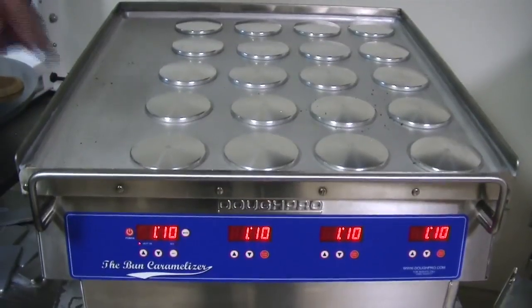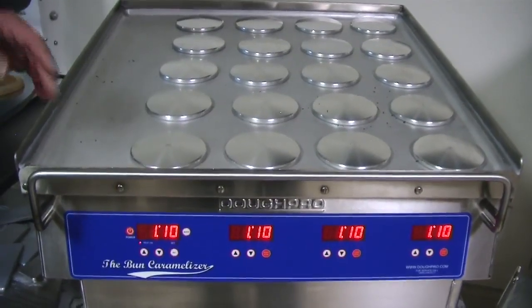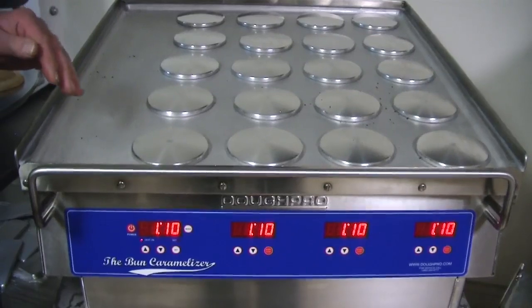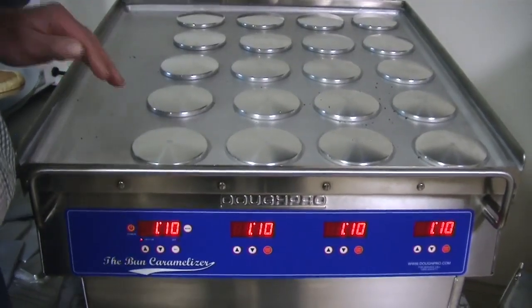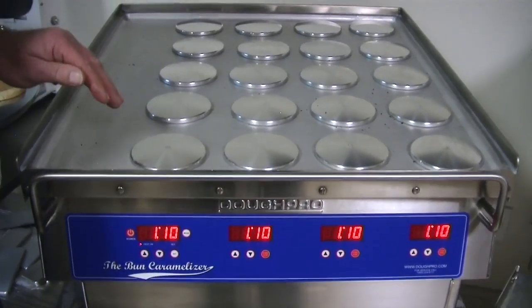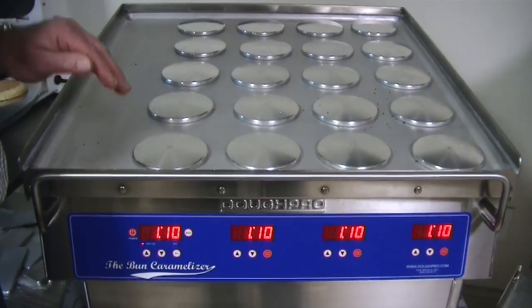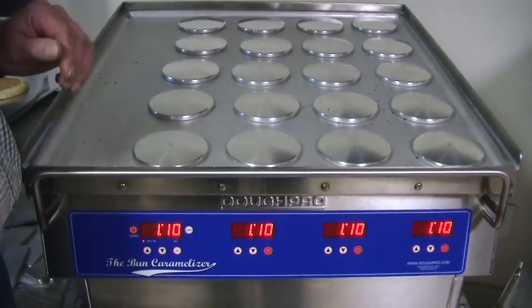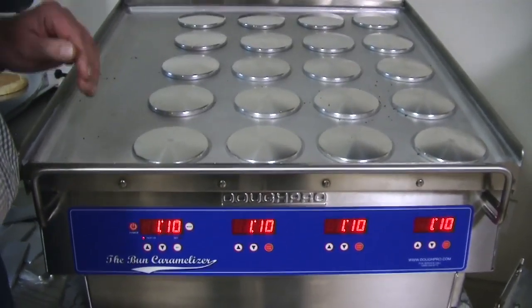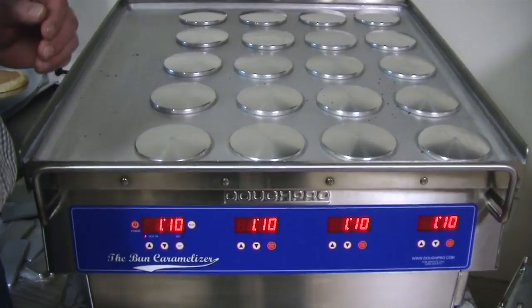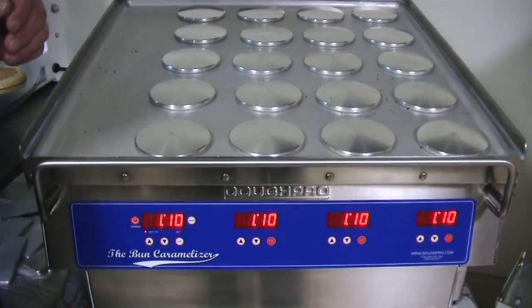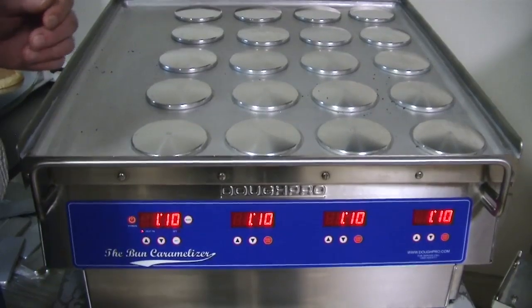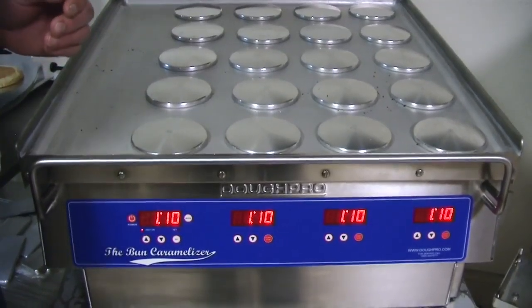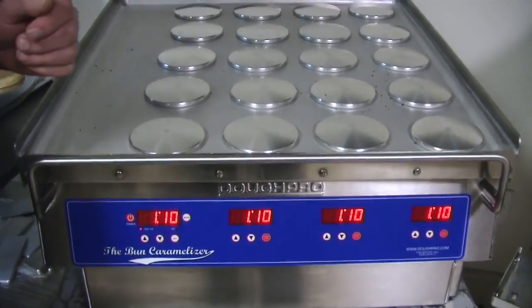This concludes DoughPro's model BC2325, 208 volt single phase, 3800 watt, 18.25 amp system. It is on a 30 amp circuit. The plug's 30 amp, so as to comply with the 125% overage of standard amp loading rate. Thank you.